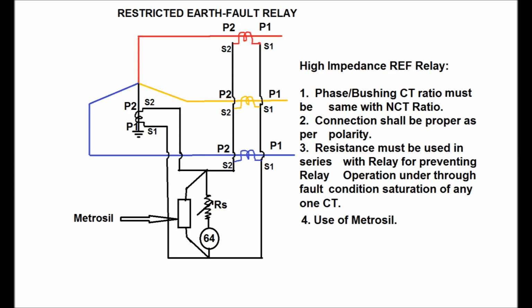The second one is that the connection shall be proper as per polarity, that is P1 shall be connected to the bus side and P2 shall be connected towards the transformer for phase CT or bushing CT, and for the neutral CT, P1 shall be connected towards the earth and P2 shall be connected towards the neutral point of the transformer.